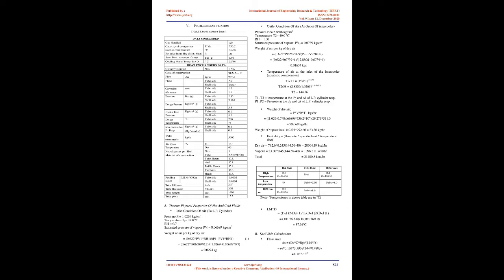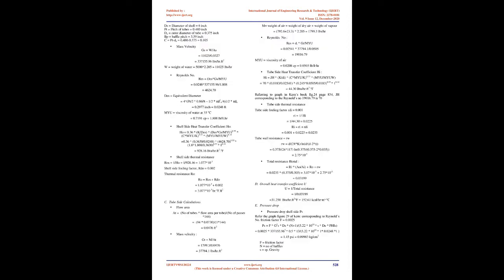Tube and tube layout. The enough tube thickness ensures that it will bear the internal pressure along with the adequate corrosion allowance. Longer tube means less shell diameter at the expense of higher shell pressure drop. Stainless steel, copper, bronze, and alloys of copper nickel are the commonly used tube materials. The shortest center-to-center distance between the adjacent tubes is pitch. The general pattern of tubes is square or triangular pattern. The tube count is the number of tubes that can be accommodated in a given shell ID. For this application triangular layout is selected as it is more effective and easy to clean.